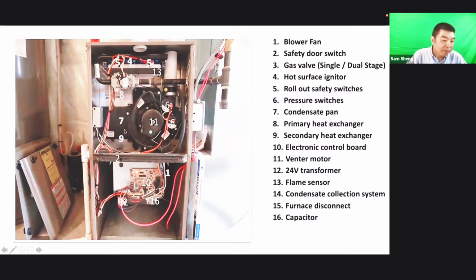That you should know. I'll make a note there too, Sam. So Sam was saying, guys, that in your installations, they do require an actual dedicated service switch for the appliance, not mounted to the appliance, but the electrical code does allow for a breaker. If there's a panel board or a breaker between the entry of the room and the furnace, that's actually acceptable. You might see that from time to time.